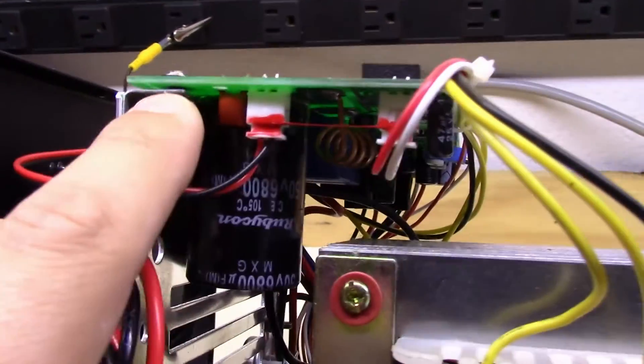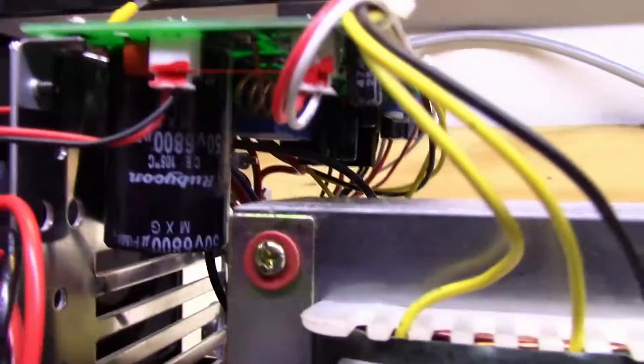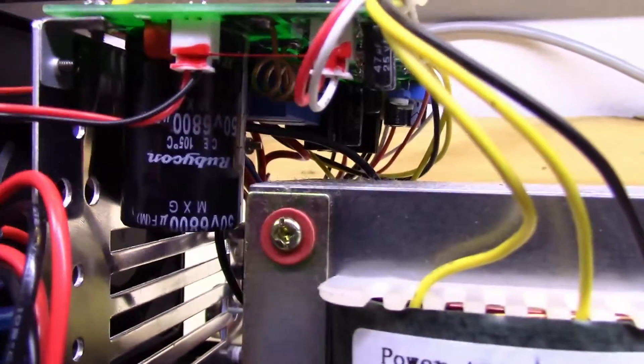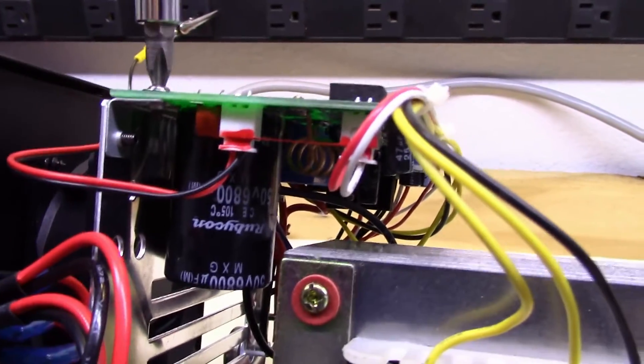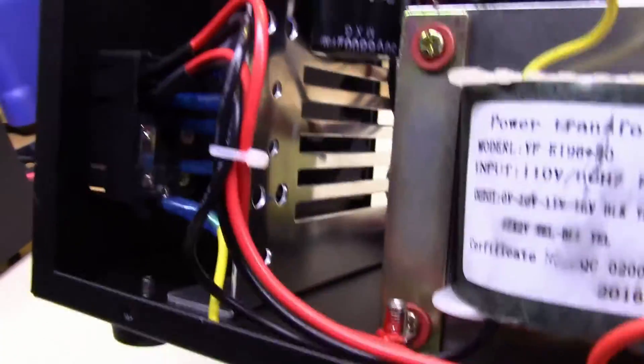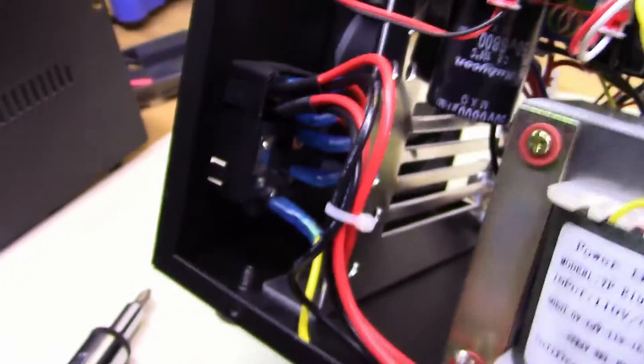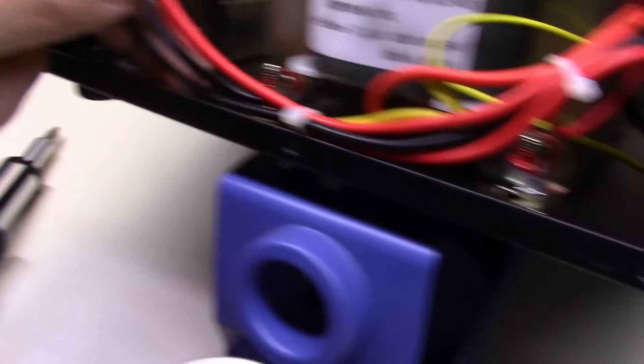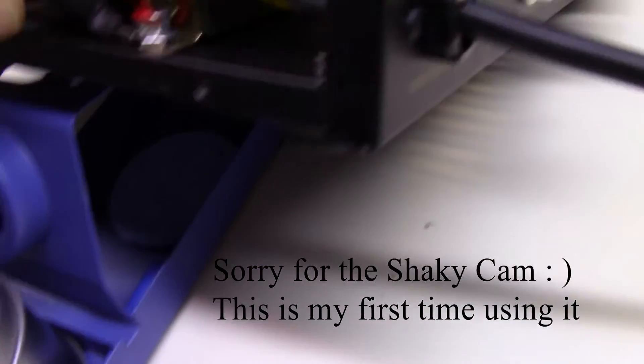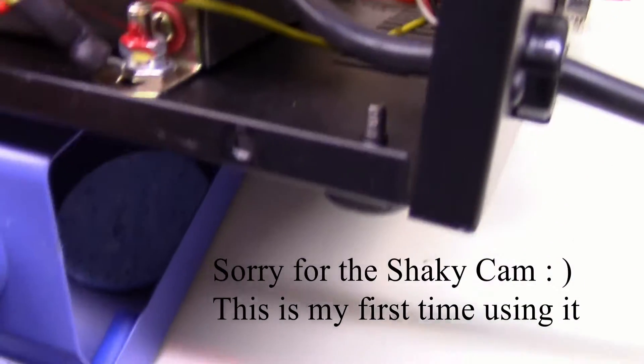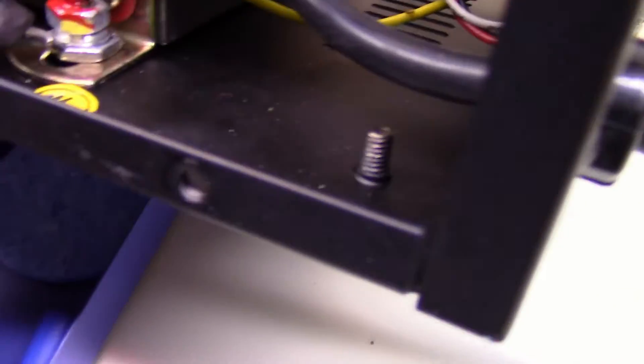We can see here we've got a screw that isn't put all the way in. I don't know if that's just, yeah see it's just loose. See I don't like, see oh it's stripped. Okay, I'll have to come back and fix that. I'll get a bigger screw and put it in there. Our main input here, we've got the main switch, wires leading off of it. Grounds are coming over to here where they are put down with a shake proof washer, which is nice.